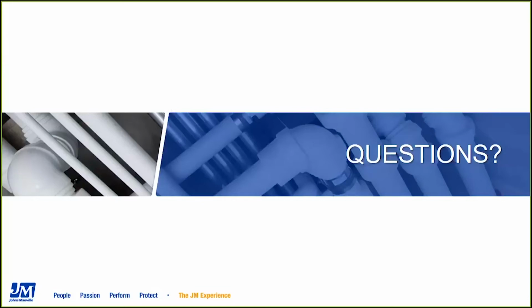Great, thank you, Sean. The next question is for you, Lance, and that is, do you have any thoughts about a combination of insulation and electric heat tracing? That's a fairly common practice for fiberglass pipe insulation, where you're trying to prevent the fluid inside of the pipe from going below a certain temperature, or maybe it's freeze protection if you've got a water system. So it's a pretty common application. With electrical, probably not as much concern around sizing. If you have something like a steam heat trace, you might have a sizing consideration where your pipe is one size, you might want a slightly different pipe size to accommodate the extra space. But yeah, very common and done quite often.